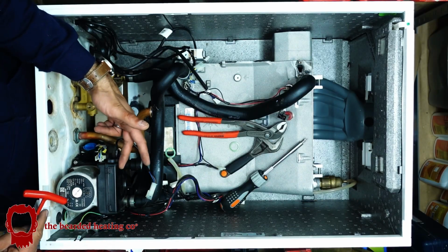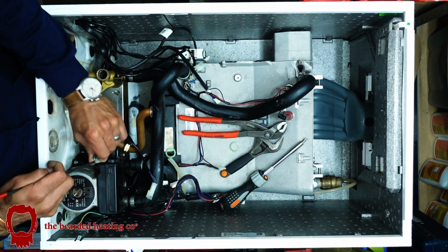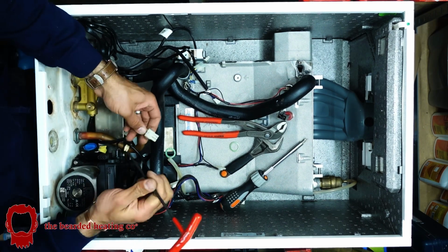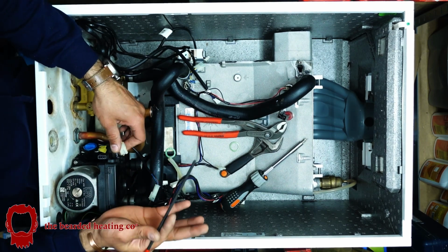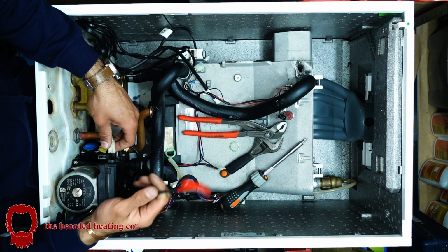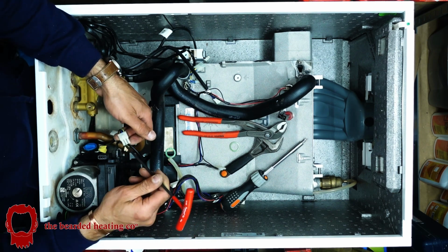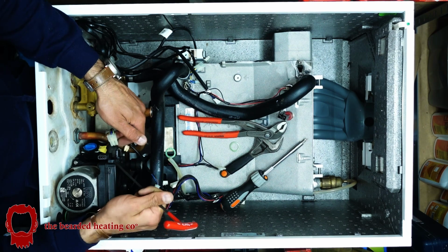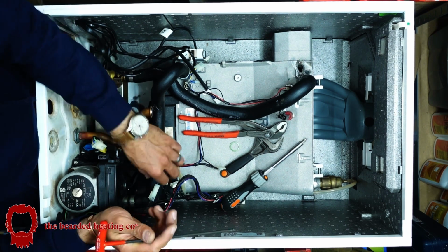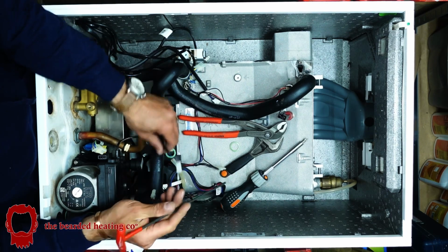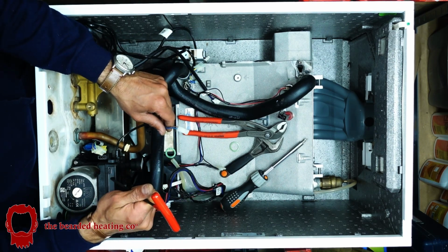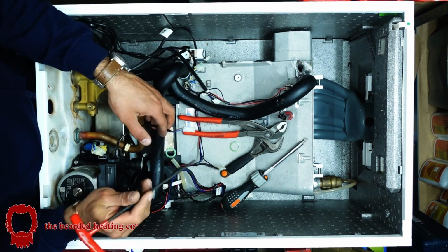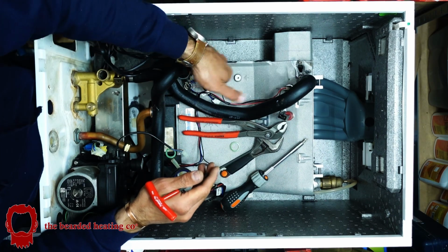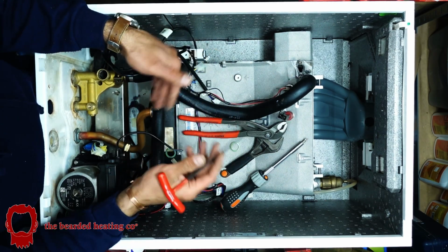The pump on the right hand side has a 230 volt connection. I don't think you'll ever come across a pump that's powered DC, because pumps need to alternate in speed - in boilers I've never come across a DC pump, it's always AC. So 230 out the way, and then this cable here, I'm pretty sure, modulates the pump speed, because there's no proving switch. I believe this boiler works with its temperature sensors, so if the temperature between the flow and return is either too similar or too far apart, it'll tell you the boiler's at fault.